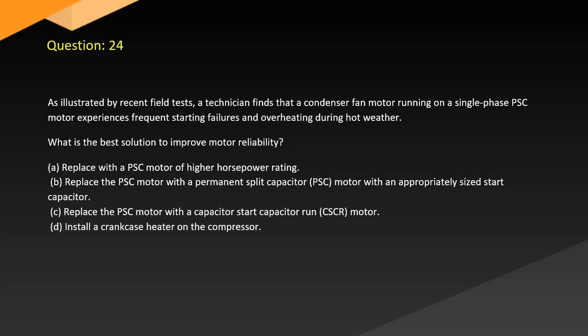Question 24. As illustrated by recent field tests, a technician finds that a condenser fan motor running on a single-phase PSC motor experiences frequent starting failures and overheating during hot weather. What is the best solution to improve motor reliability? A. Replace with a PSC motor of higher horsepower rating. B. Replace the PSC motor with a permanent split capacitor PSC motor with an appropriately sized start capacitor. C. Replace the PSC motor with a capacitor start capacitor run CSCR motor. D. Install a crankcase heater on the compressor.